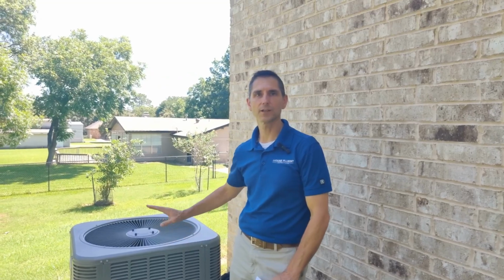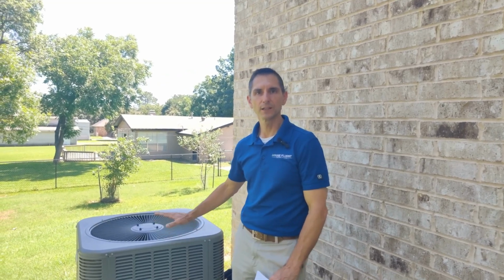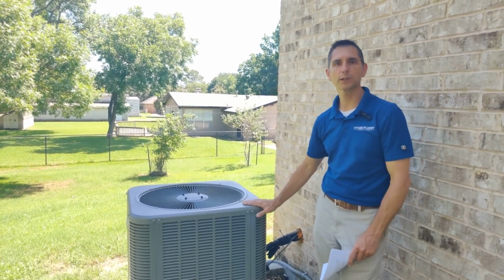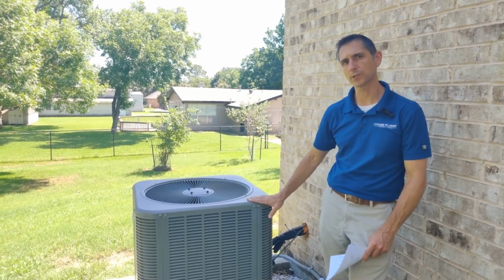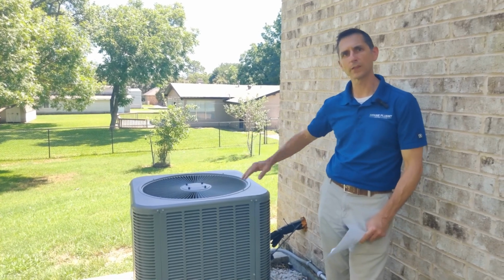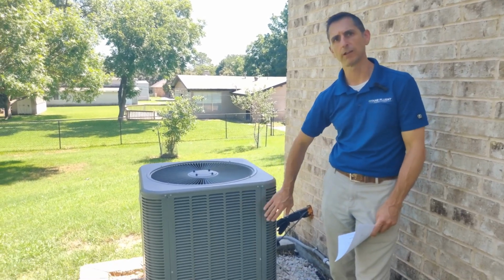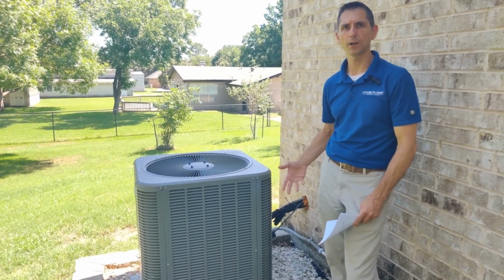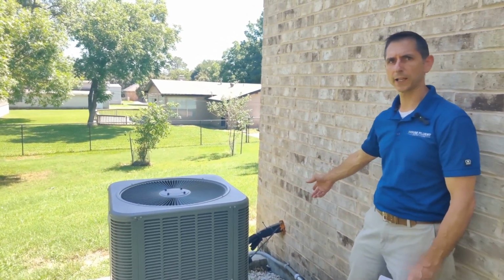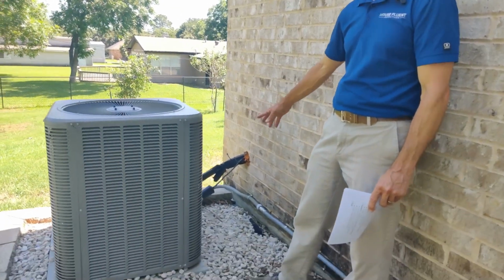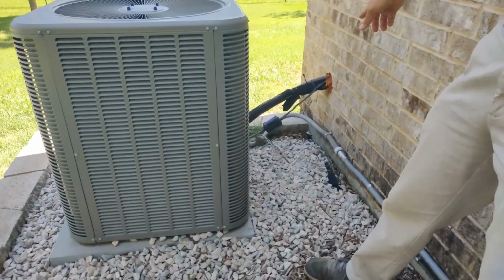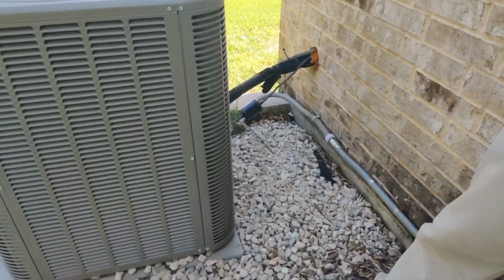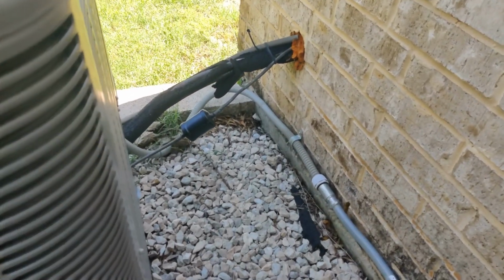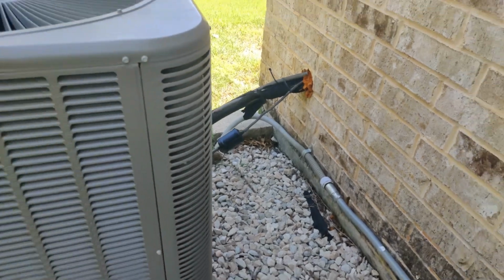Next, take a look at your HVAC unit. There's not much to do with the compressor in springtime, just a visual inspection. Walk around it and look for things like fin damage that may have occurred. You'll also want to check the insulation and make sure it isn't torn up like this one is. You can see there's quite a bit of damage here, so that black pipe insulation needs to be replaced.